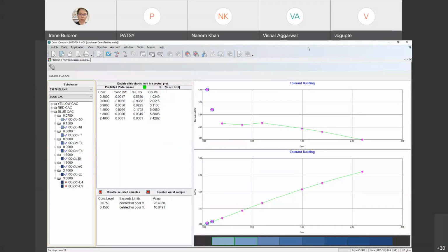Otherwise, even if you measure 4 times and average, it doesn't really represent this particular percentage, and you end up without a good sample in the database. So just make sure you understand what samples are needed, not as many as possible. In the software, the maximum is only 15 levels. If you have more than 15 levels, the software will just ignore it, or in another way, we also see some weird performance. So just a small reminder for everyone.